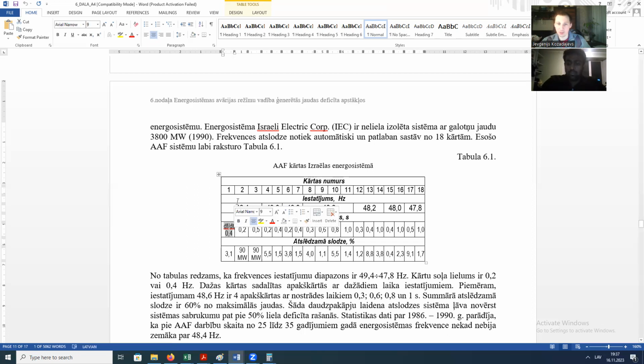For example, we have not reached the next set point, but we could see that we have a high frequency decrease speed, and we could start to disconnect faster, quicker, not waiting to reach the next set point. This is the idea.